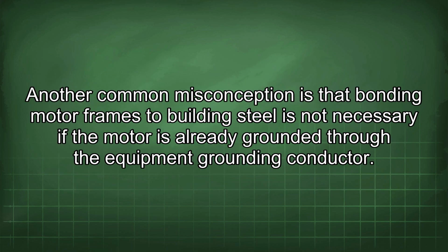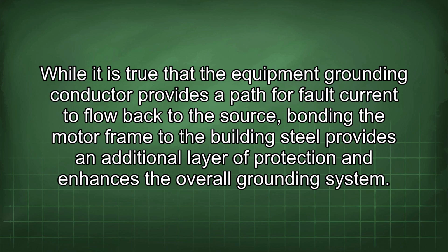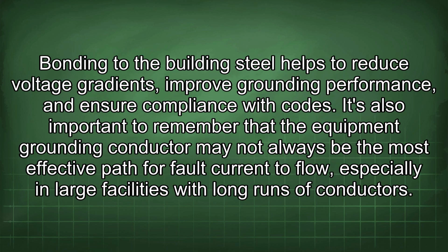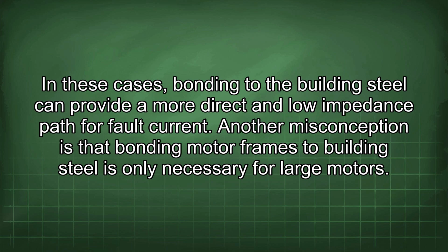Another common misconception is that bonding motor frames to building steel is not necessary if the motor is already grounded through the equipment grounding conductor. While it is true that the equipment grounding conductor provides a path for fault current to flow back to the source, bonding the motor frame to the building steel provides an additional layer of protection and enhances the overall grounding system. Bonding to the building steel helps to reduce voltage gradients, improve grounding performance, and ensure compliance with codes. It's also important to remember that the equipment grounding conductor may not always be the most effective path for fault current to flow, especially in large facilities with long runs of conductors. In these cases, bonding to the building steel can provide a more direct and low impedance path for fault current.